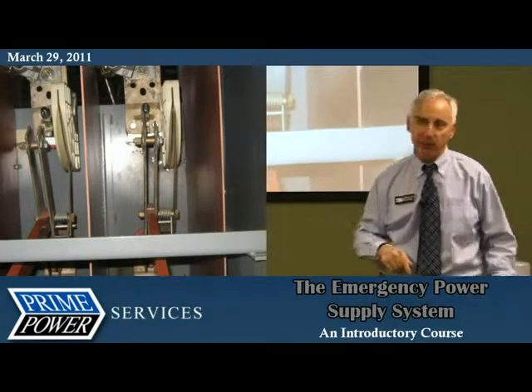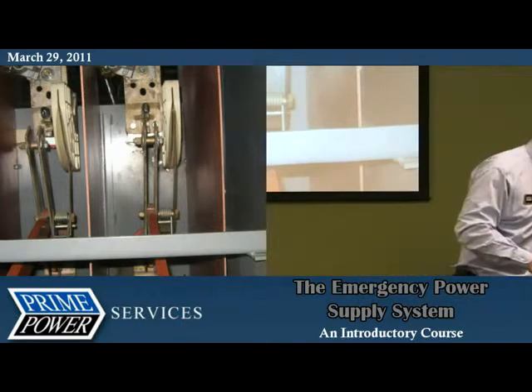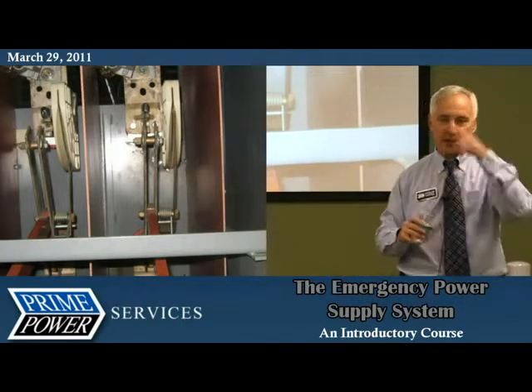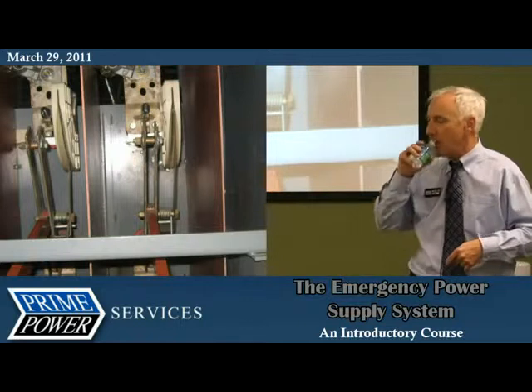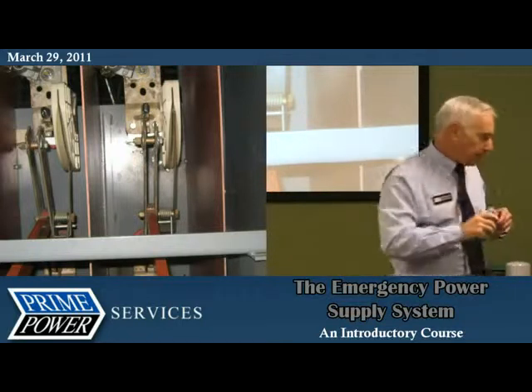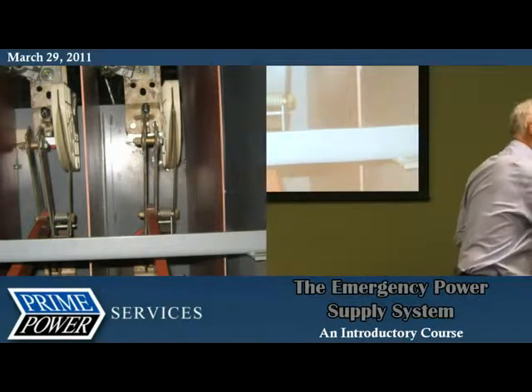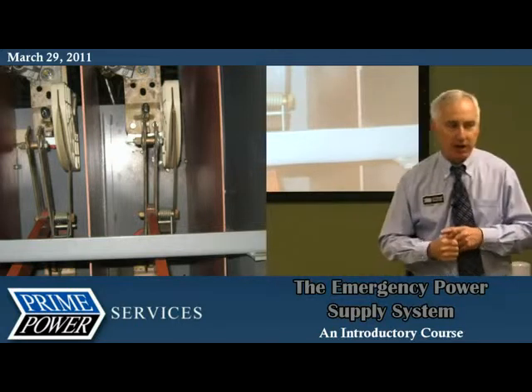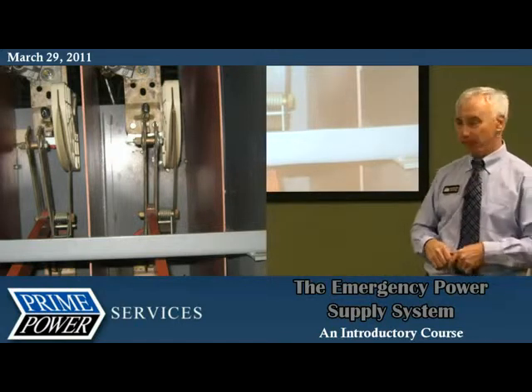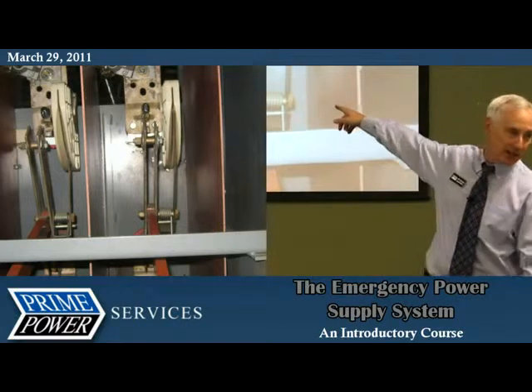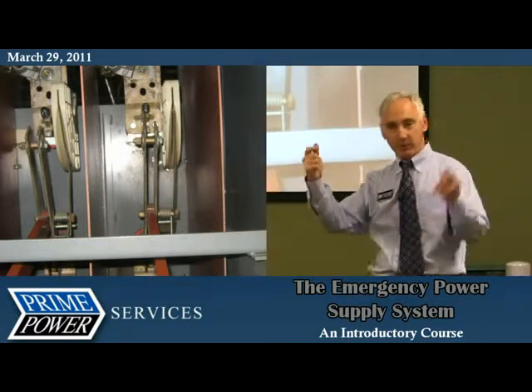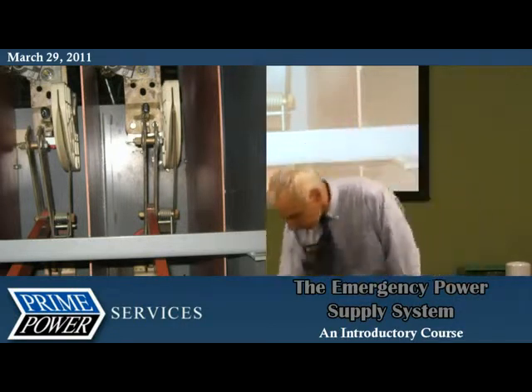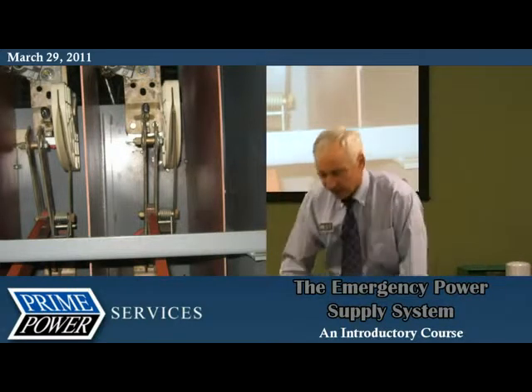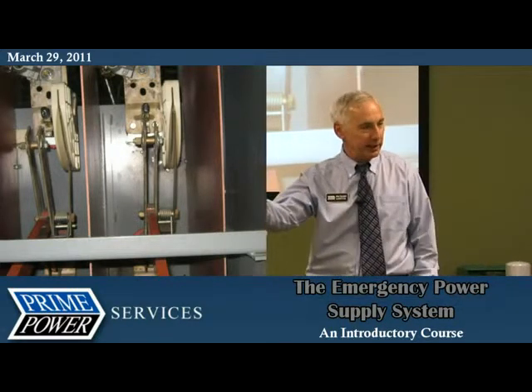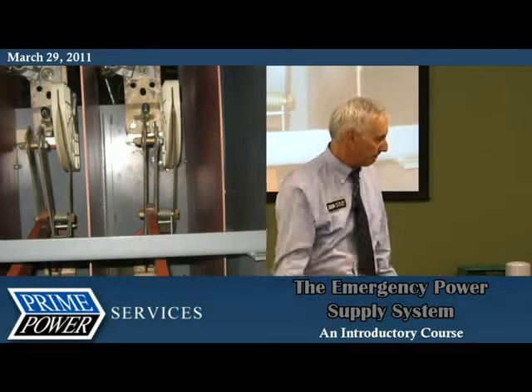The site electrician, being a good electrician, knew there's capacitance on this wire. So he decides to bleed off the capacitance in this wire. So the switch is open. Unbeknownst to him, one of these is closed. He takes his jumper, his little 10-gauge jumper, connects it to ground, and the other one he puts on a wire here.